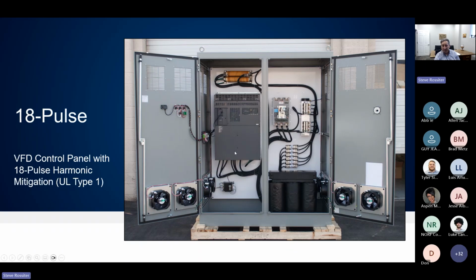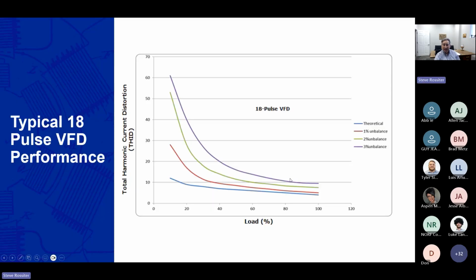existing regular 6-pulse drive that has one set of diode rectifiers. And again, pretty good harmonics, down close to that 5% range, unless you have big voltage imbalance. And if you're at 50% load or better, still pretty good reduction.